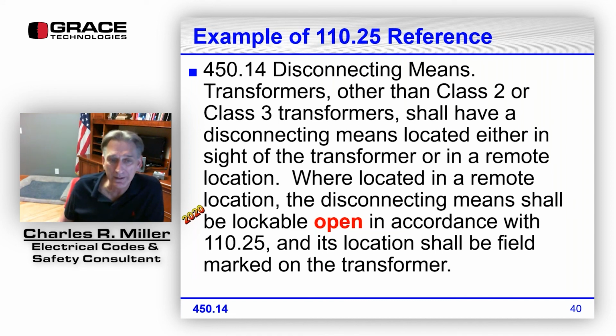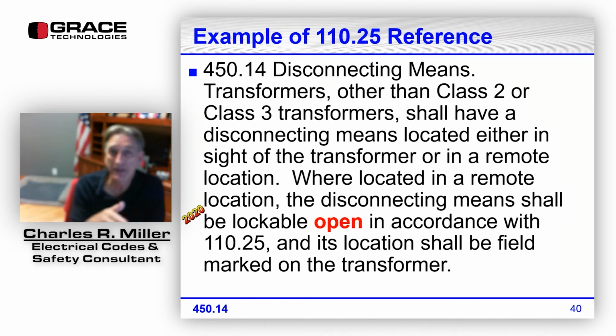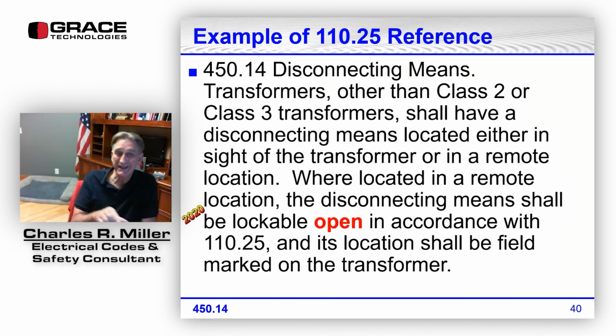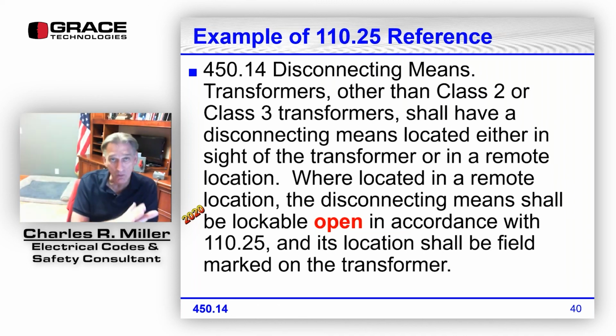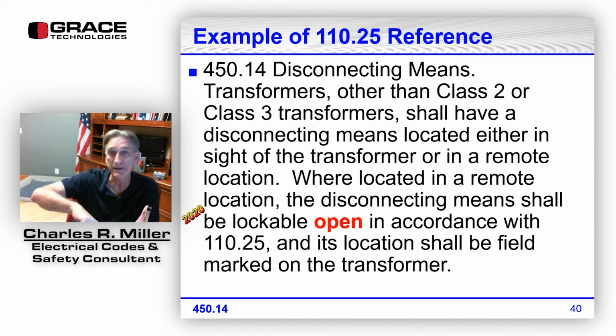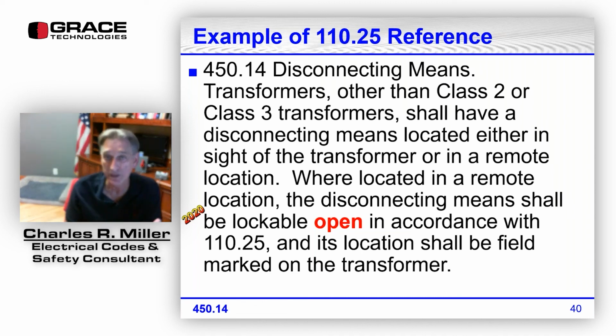It has to be lockable open in accordance with 110.25, and its location has to be field marked on the transformer. All right, so in that case, if there were not a disconnecting means within sight of a transformer, like one of my illustrations earlier, then it would have to have that. The disconnecting means would have to be lockable in the open or off position. Well, actual safety switches for many years now have had to be manufactured where they could be locked in the off or open position.